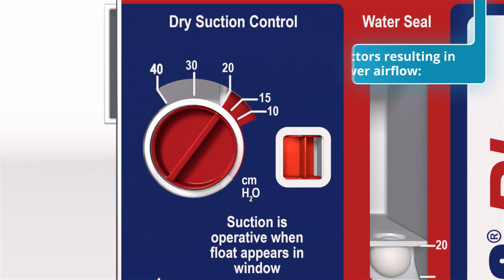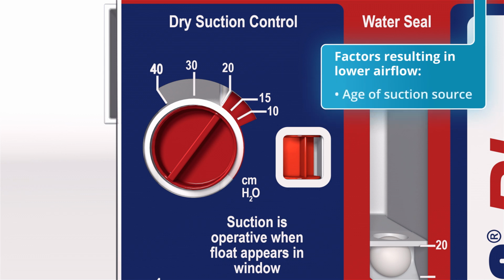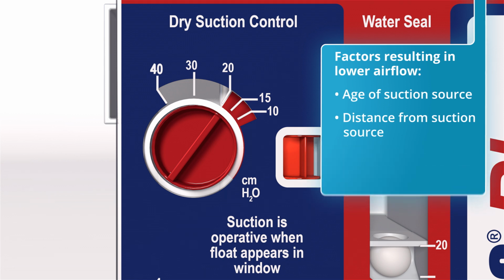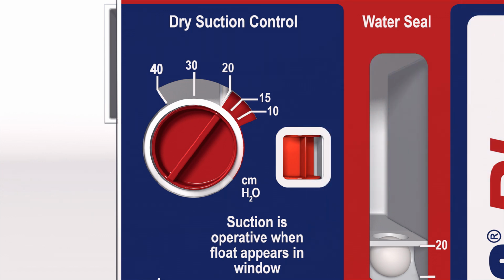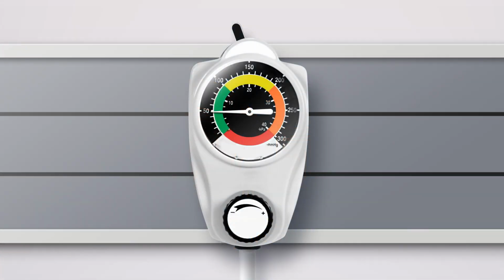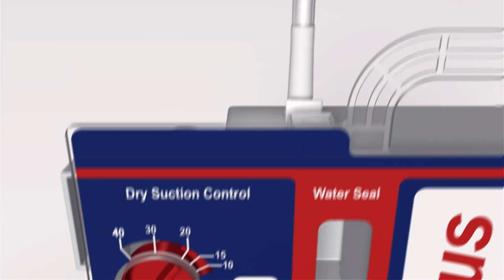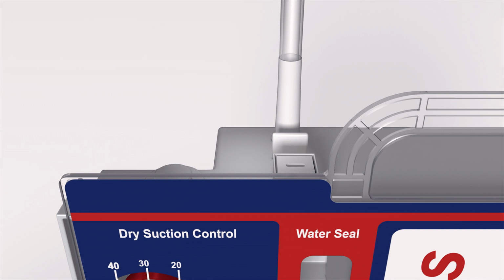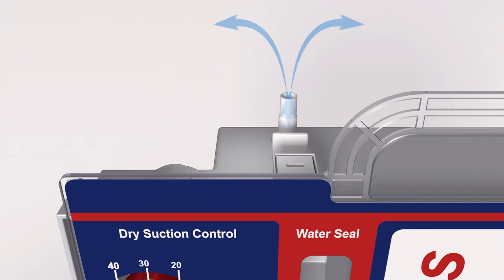Certain factors may result in lower source airflow, delivering lower than prescribed suction to the patient's pleural space. These factors include, but are not limited to, the age of the suction source, distance from the source, and number of devices connected to the source. For this reason, and thanks to the regulator, suction can be turned up as high as necessary to offset low airflow and actuate the orange float, visually confirming adequate airflow has been achieved. Monitoring of the source to confirm proper function should be a secondary indicator of accurate suction and airflow. When suction is not being used, it is essential to keep the suction tube and port uncapped and unclamped. This allows air to exit freely from the patient, reducing the risk of pneumothorax.